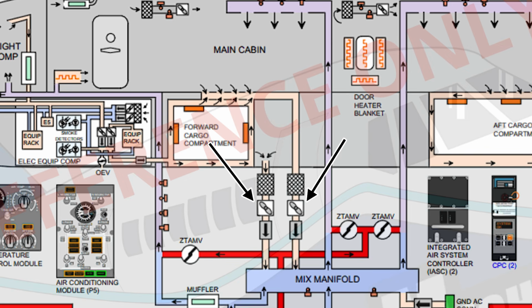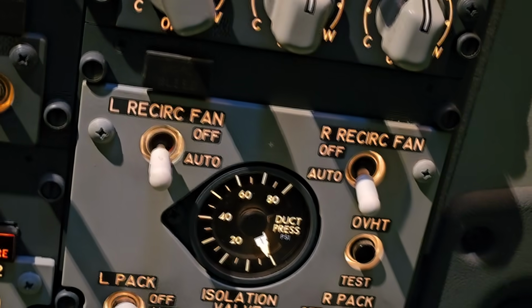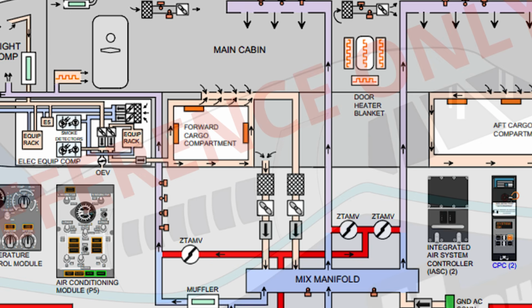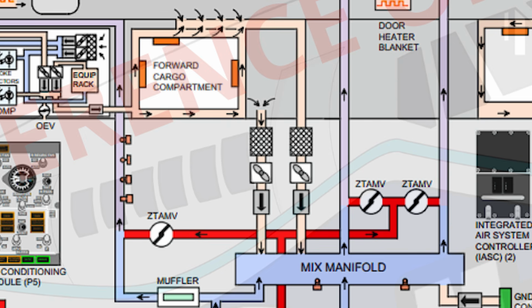Now let's check out the recirculation fans. These fans are there for ventilation and to cut down on how much air we need from the engine bleed air system. There are two of them, one on the left and one on the right. They pull air from between the two cargo compartments and from the cabin through a filter. This filter is a high efficiency particulate air, or HEPA, filter, which means it's super good at removing tiny particles and bacteria from the recirculation air. Then this air gets sent back into the mix manifold. Because we are reusing this air, it takes some of the pressure off the air conditioning system.